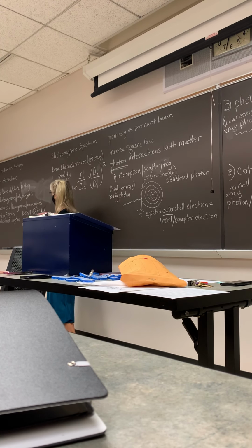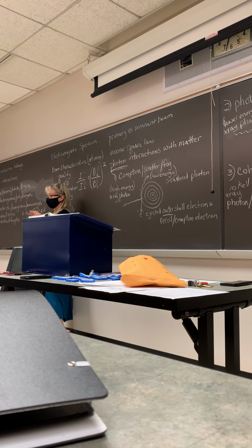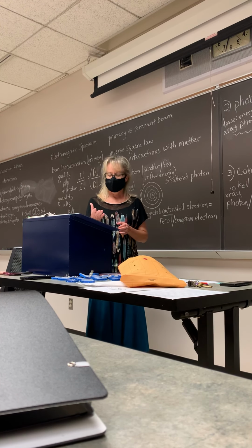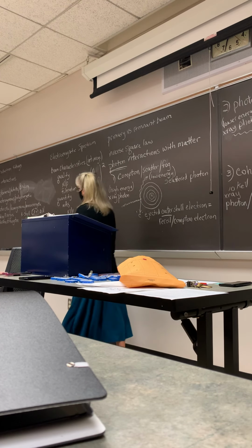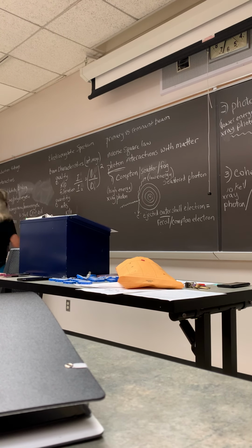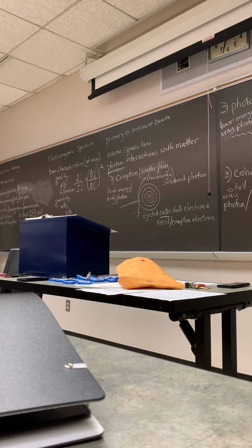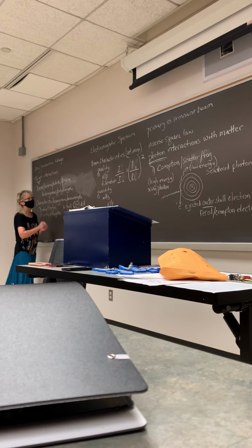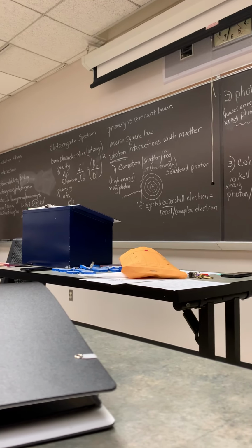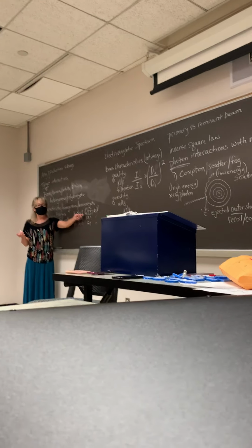All right, so the electron comes over and it interacts with the K shell of tungsten. What's the atomic number of tungsten? 74. So the atomic number is 74, and the shells coming from the nucleus out get less and less binding energy. So the electron comes over and knocks this K shell electron out. Then one of these other shells, or maybe a free electron, will go in and fill the gap.